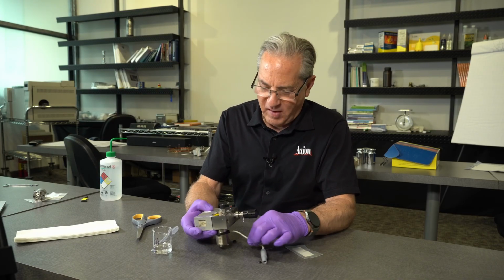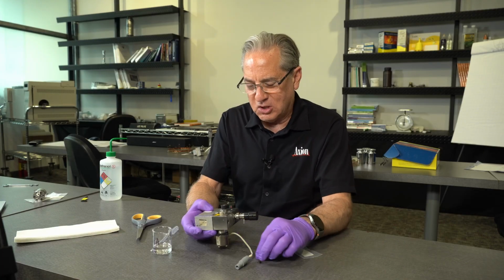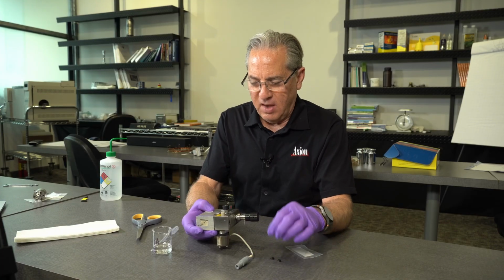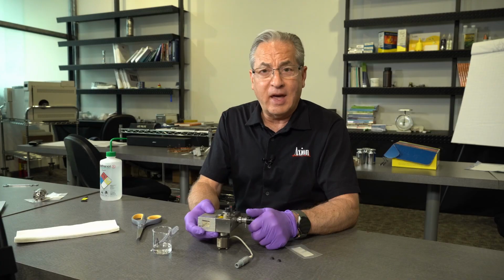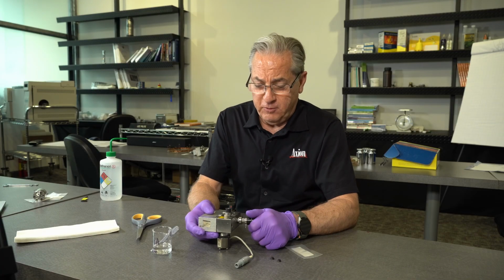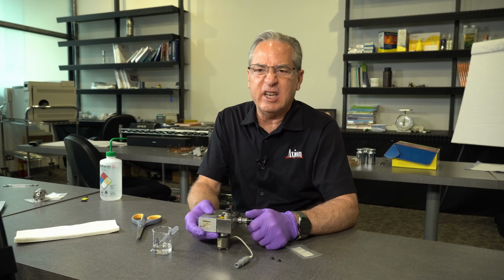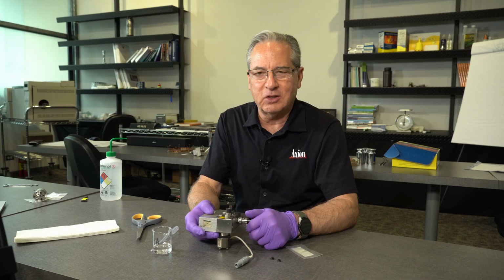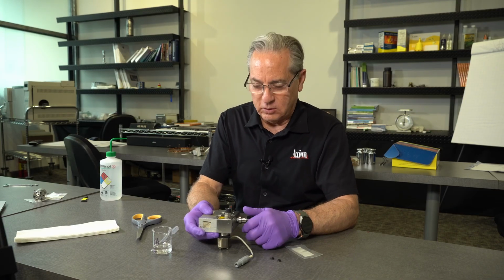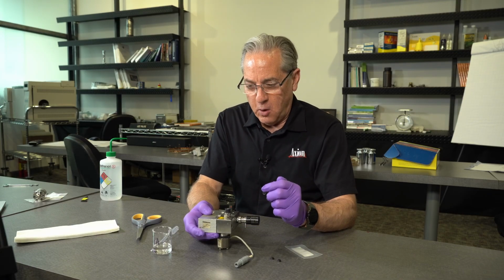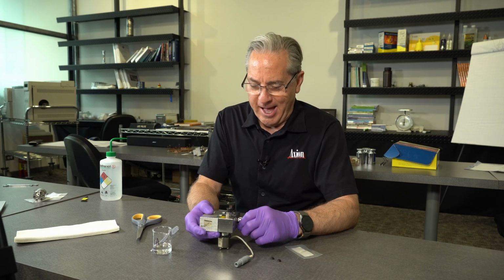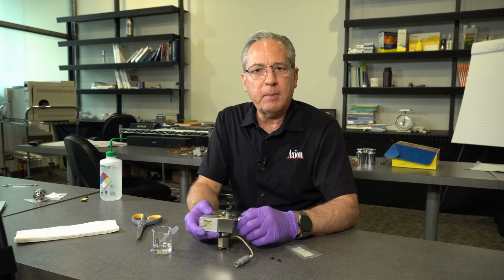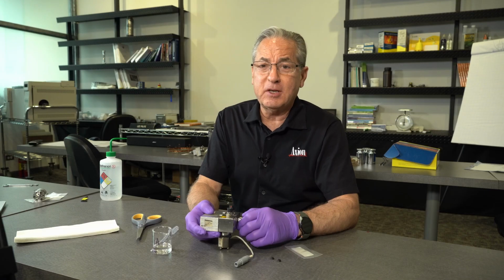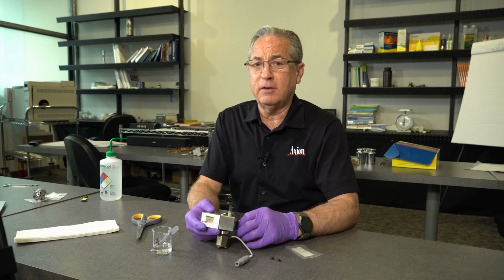There's an old-fashioned approach called the seal wear-in procedure. I don't believe in it. If you start with the seals wet, you will not have a problem. If you start with the seals dry, you've got a 50-50 chance of it working. Then you have to do a special procedure to set the seals, is what they call it. So wet them with isopropanol and follow that procedure, and you'll be able to change any pump seal on any pump out there known to man.